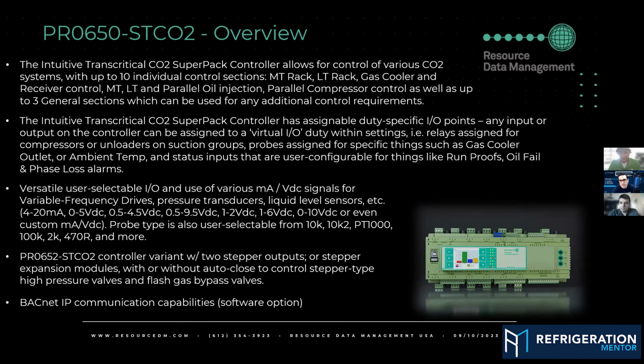Yep. And then there are variants of this controller. There's a 650 style, which is just the software for doing control. There's also a 652 variant of the controller. It has two stepper outputs on it for your high pressure valve and your flash gas bypass valve. You can do stepper type valves, or you can do 0 to 10. And there's a third option for a heat recovery, heat reclaim valve. You can do that either 0 to 10 or stepper type as well.